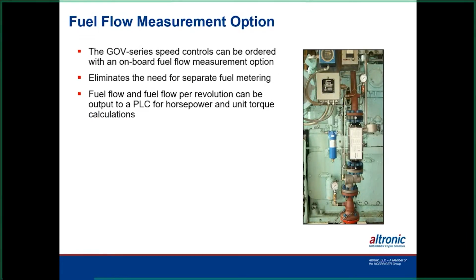And then the fuel part up there, we talked about that. That is an option that comes with the valve. Again, we require the piping to be fairly straight in and out of that to give us a good, accurate reading on that. And it also can be calibrated with the controls in the valve there. If you have a way of measuring the fuel gas going into it, maybe on another source at the plant somewhere, then you can calibrate the valve for that. And then these numbers can be used for either calculating horsepower or torque calculations on the engine.